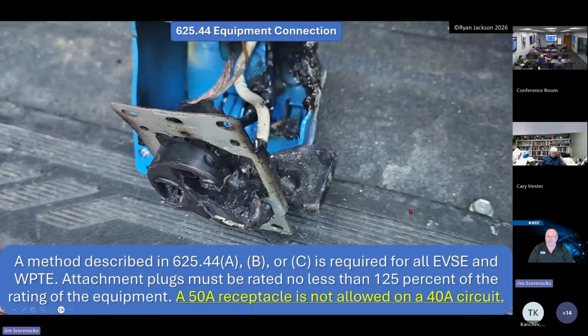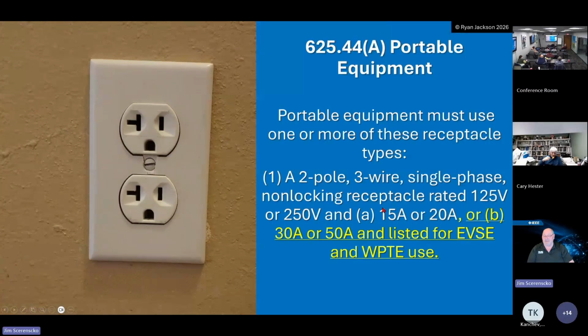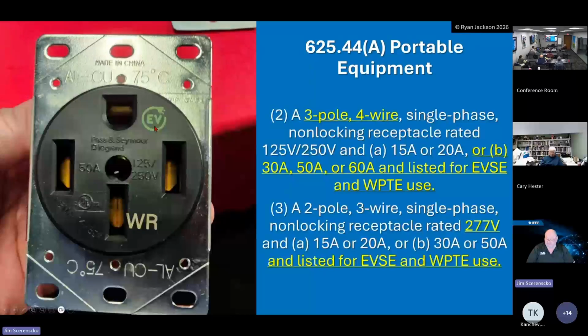Well, I don't know if it's a receptacle that's rated higher than 50 amps. I don't think there's a 60 amp. It doesn't apply to 2-pole, 3-wire, single-phase, non-locking receptacles rated 125 volts, 250 volts, 15 or 20 amp, or 30 amp or 50 amp listed EVSE WPTE use. So they make a receptacle now that has this little design on it. It's specifically designed to withstand the constant, continuous loads of the EV charging, because it has become a big problem.